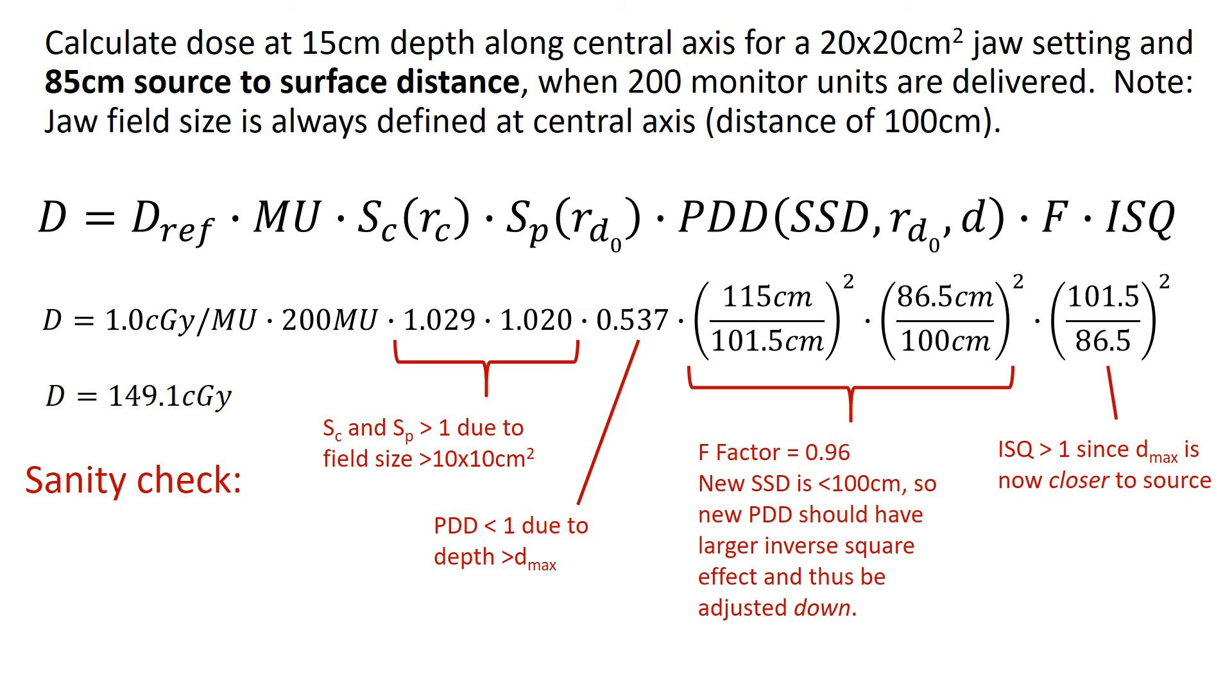And then finally, our inverse square correction is greater than 1. And this makes sense because that normalization point went from 100 cm SSD plus D max to 85 cm SSD plus D max. So it got quite a bit closer, so we would expect that to bump up the output to that normalization point.